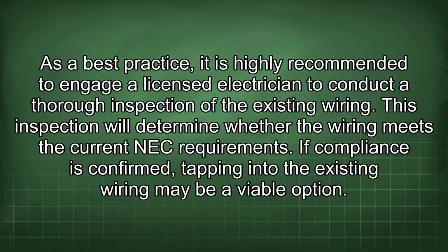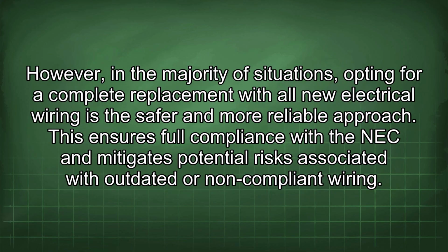As a best practice, it is highly recommended to engage a licensed electrician to conduct a thorough inspection of the existing wiring. This inspection will determine whether the wiring meets the current NEC requirements. If compliance is confirmed, tapping into the existing wiring may be a viable option. However, in the majority of situations, opting for a complete replacement with all new electrical wiring is the safer and more reliable approach. This ensures full compliance with the NEC and mitigates potential risks associated with outdated or non-compliant wiring.